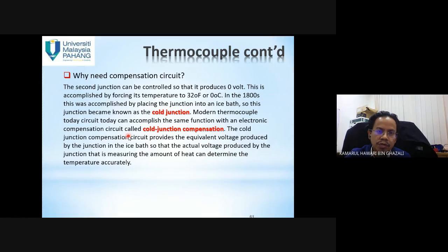So why do we need to do the compensation? The second junction can be controlled so that it produces 0 volts. This is accomplished by forcing its temperature to 32 degrees Fahrenheit or 0 degrees Celsius. Okay, in the 1800s, this was accomplished by placing the junction into an ice bath. So this is how the thermocouple compensation was done. So the junction became known as the cold junction.